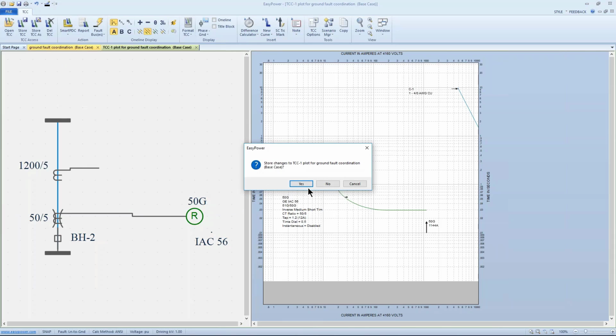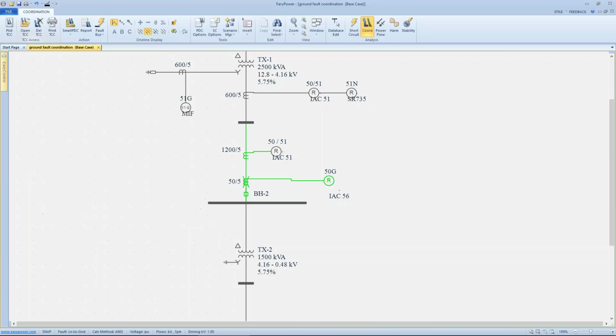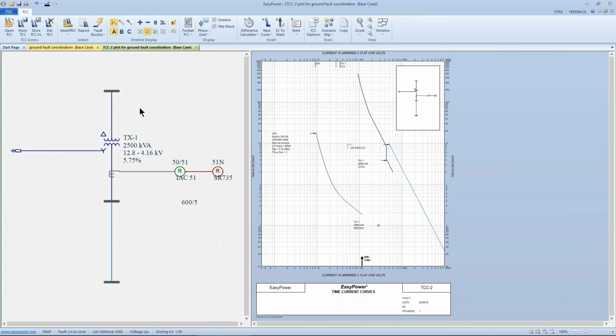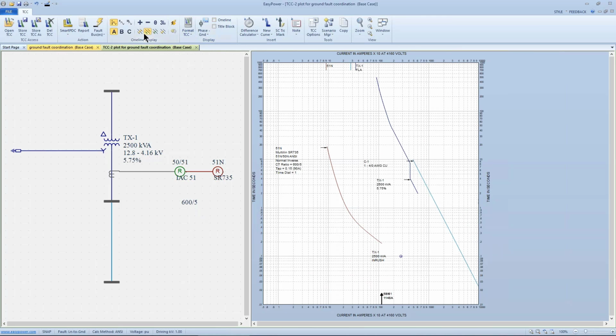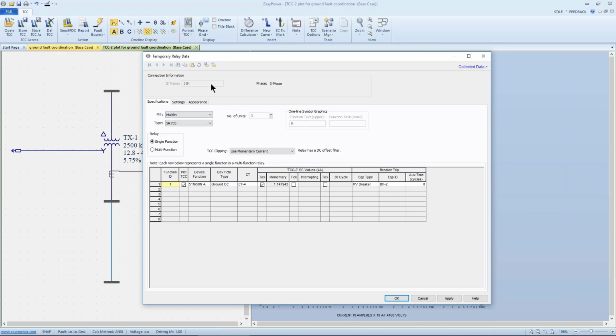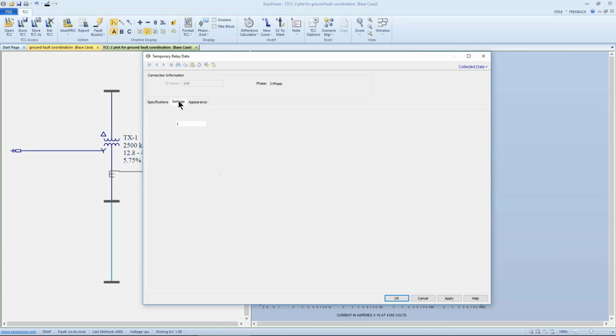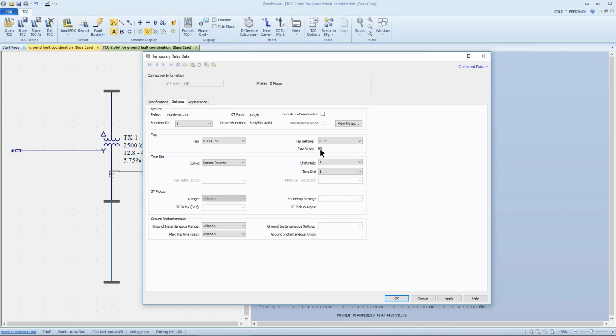Then our next level is the 51N, which is this relay up here. And if we expand that, apply a single line to ground fault. In this case, we've chosen a Multilin 735 and a 51N ground overcurrent. And the settings here were, we want to set it at 25% of the rating. The NGR rating of the resistor is 1200 amps. So let's set this at 300.